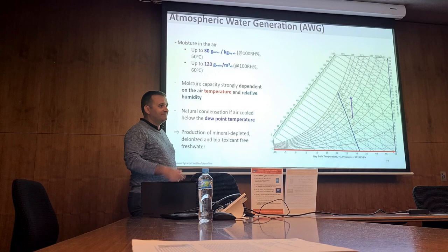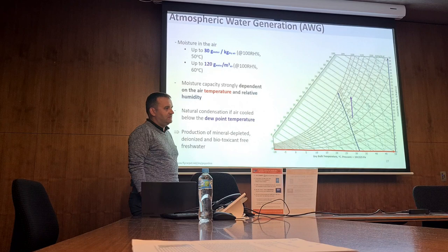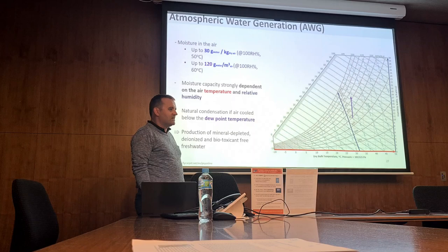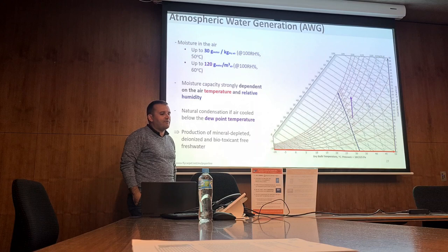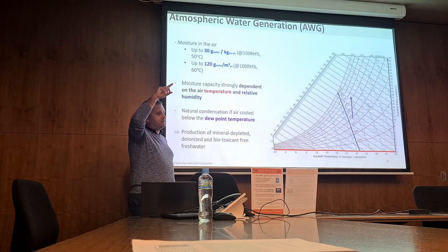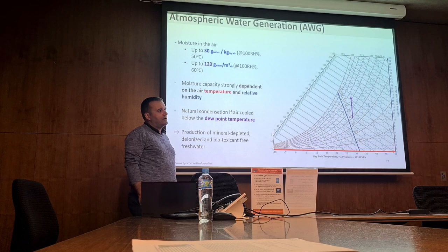Is there a difference between the water generation at night and daytime? Yep. It's much, much higher at night, obviously, because the temperature goes down and so your RH relatively goes up. But when we have 70% humidity during the day, even at 45 degrees, we still get a lot of water, but the production is not linear. It's not even over the day. We get a peak from 8, 9 p.m. until 5 a.m., and then we have a dip.